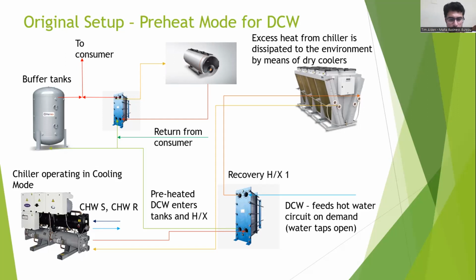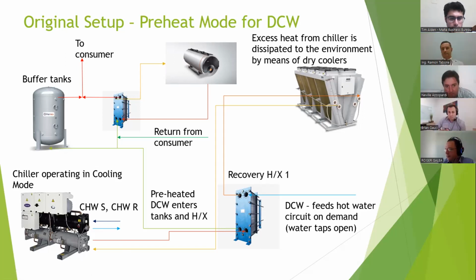What's another disadvantage of the system? The load is intermittent, which means you don't have cold water coming in continuously. So to stabilize the chiller, you had to have dry coolers above, which are the ones here. When you don't have demand for hot water, the extra heat generated by the chiller is dissipated into ambient. Otherwise, it will go on over temperature, over pressure, and the chiller will trip.